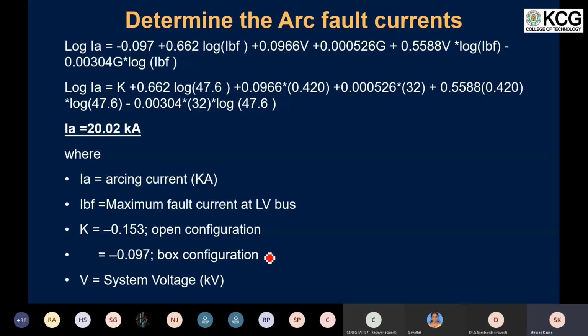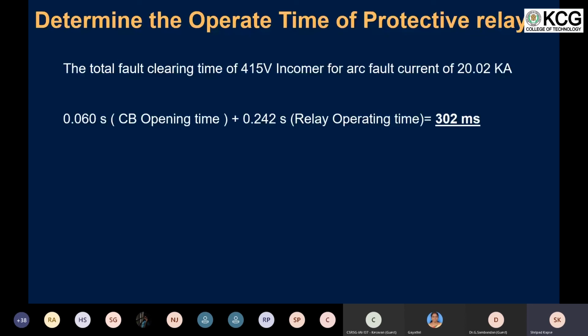So IEEE 1584 provided us the guidelines to calculate this, and then we determined the operating time of the breaker and the operating time of the relay if the arc flash protection was not there. If the arc flash protection was not there, the relay would operate on an IDMT based coordinated system. So in the inverse definite time overcurrent, we would find that the overall fault clearing time from the relay would come around 242 millisecond, and if you add another 60 millisecond of the breaker opening time, it would come around 302 millisecond as overall fault clearing time.